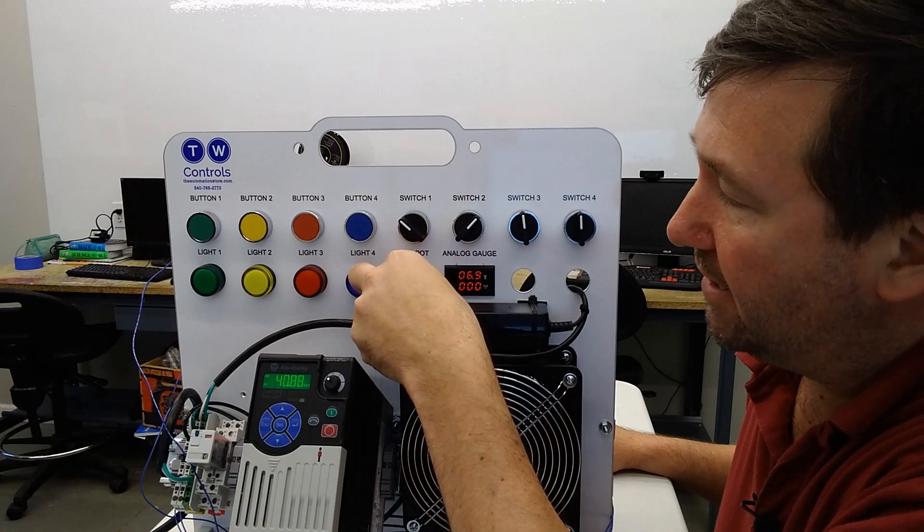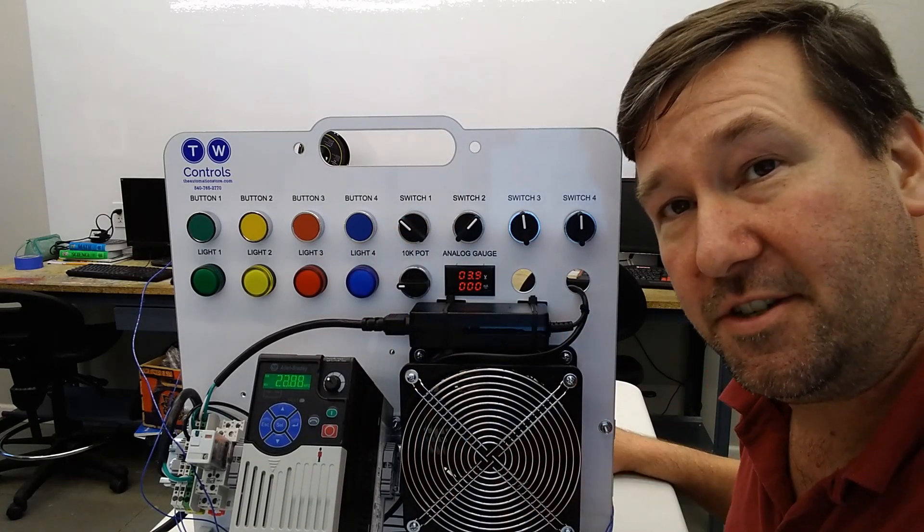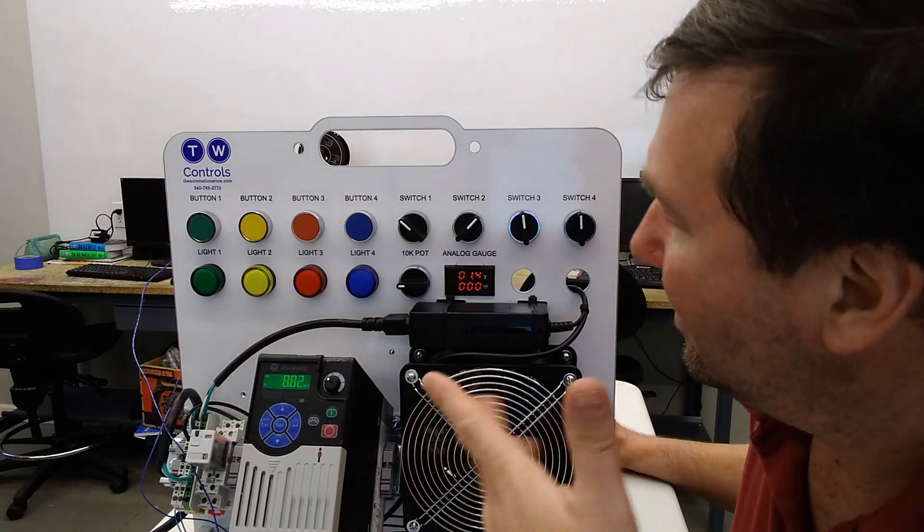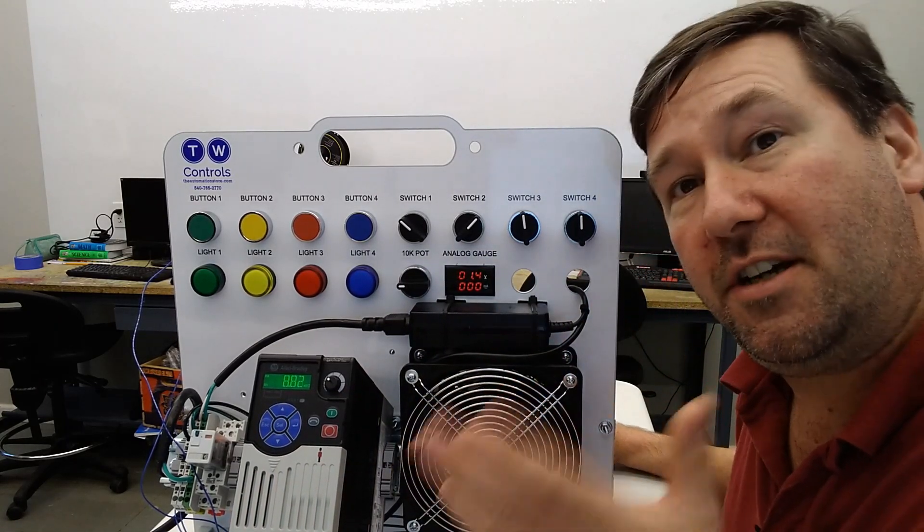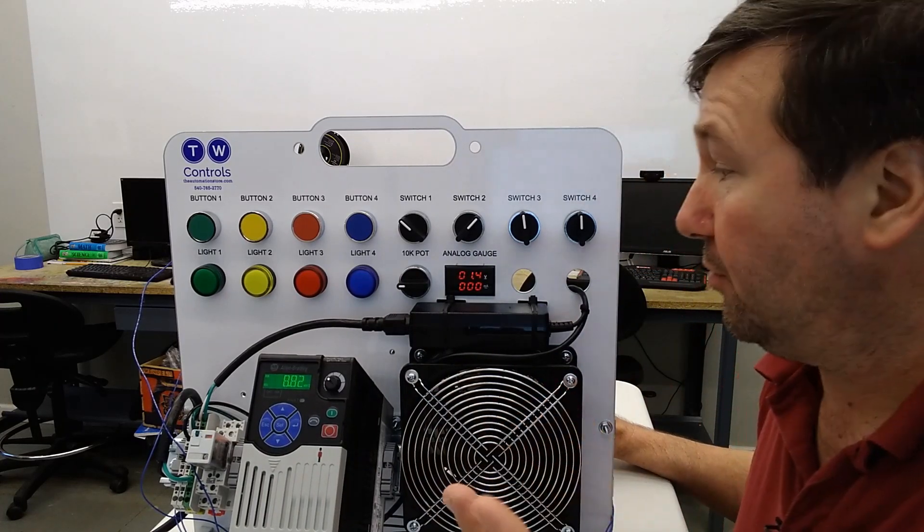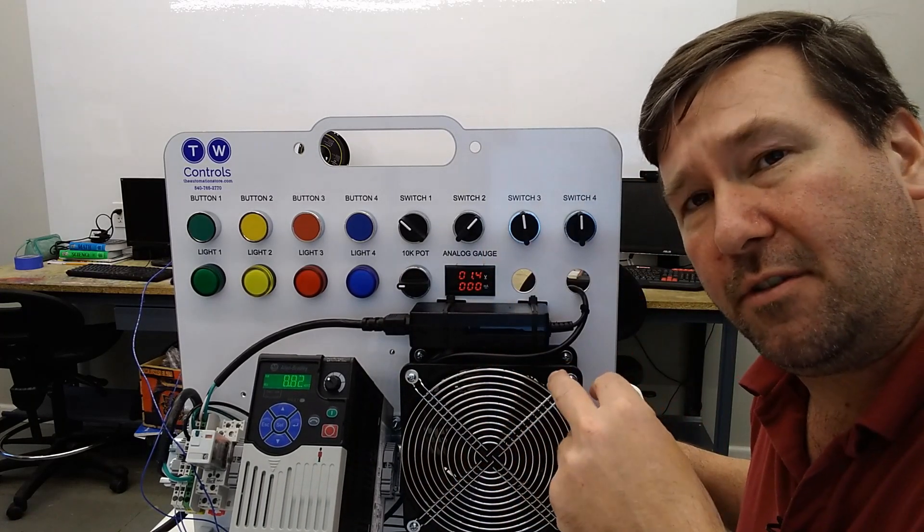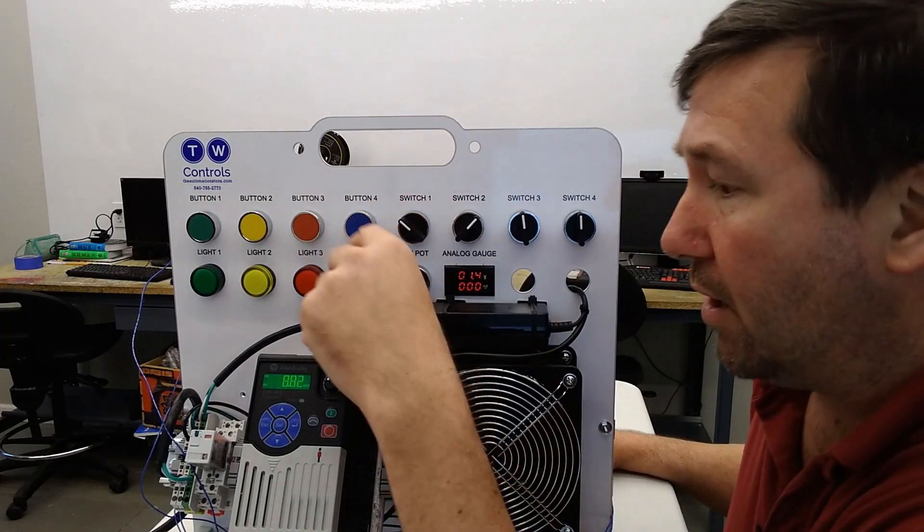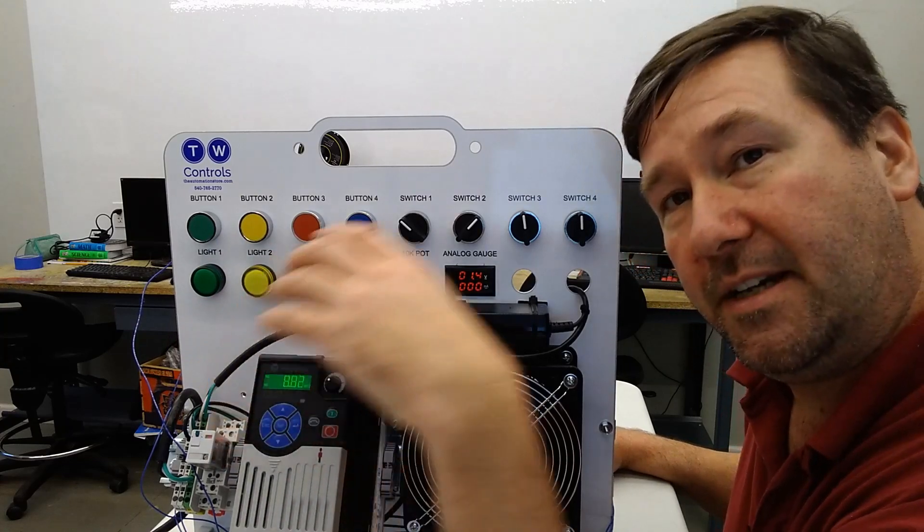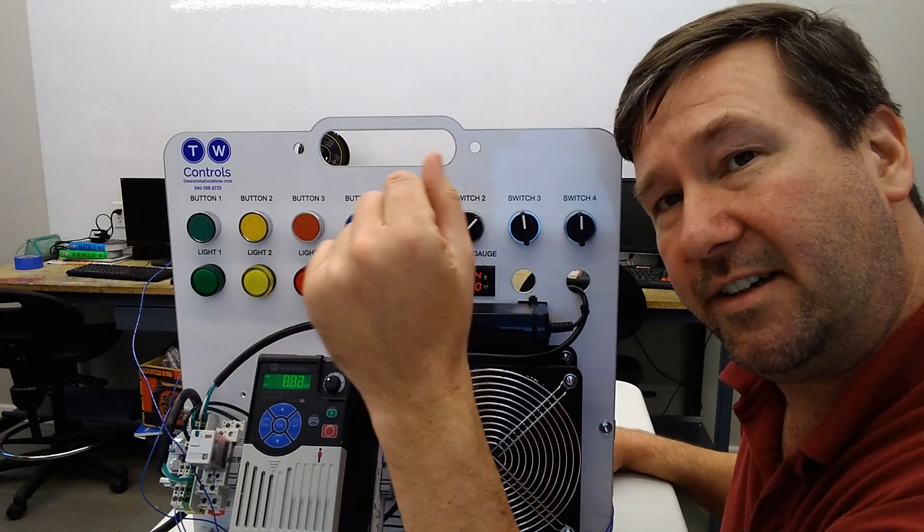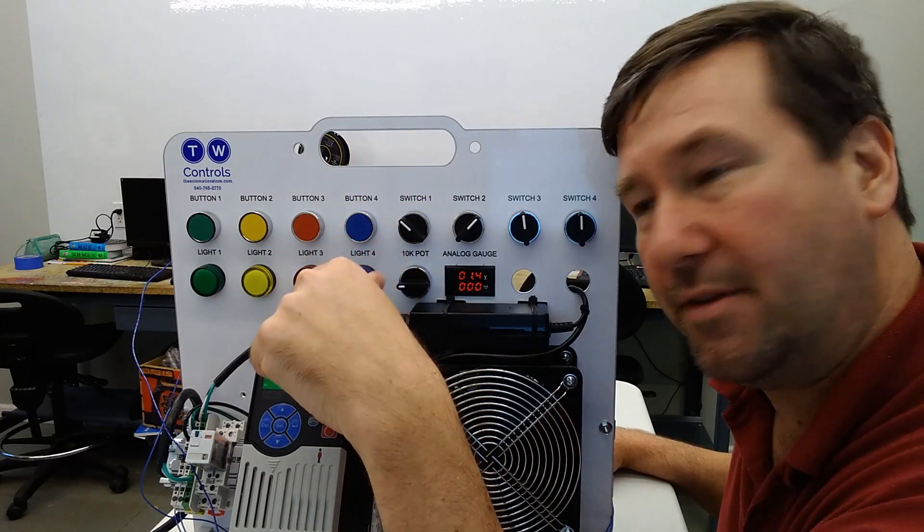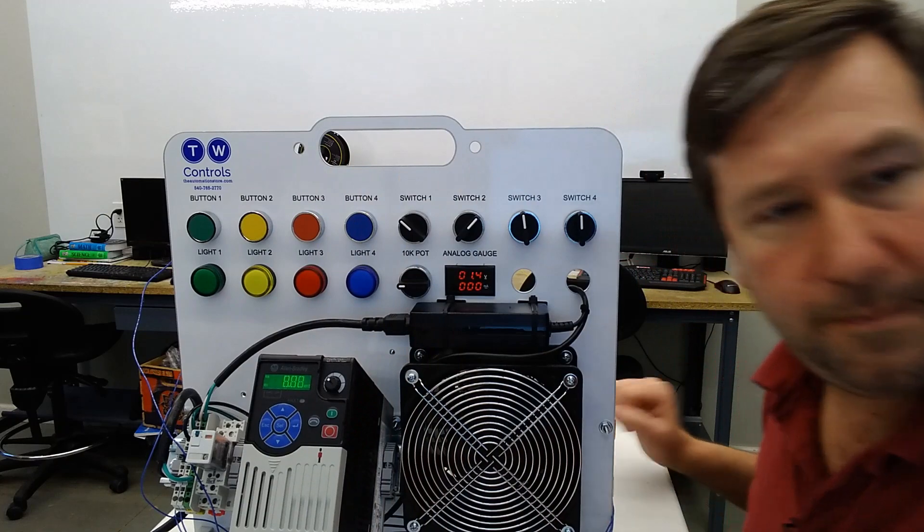And let's bring it down, somewhere down mainly in the range that you can hear now. We're running 8 hertz and it's about 1.4 volts. So you can take this on to a PLC input or to say, the command input of another drive. Actually, yeah, I need to put that on the list. That would be a really good video where you have one drive commanding the speed to another drive. That's actually a common thing I see and I should do that. So I'm going to go put that on the list.